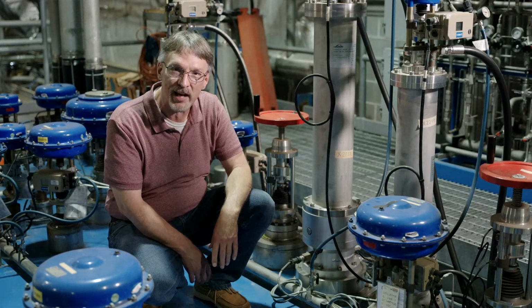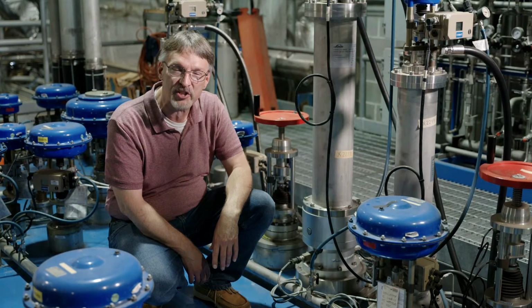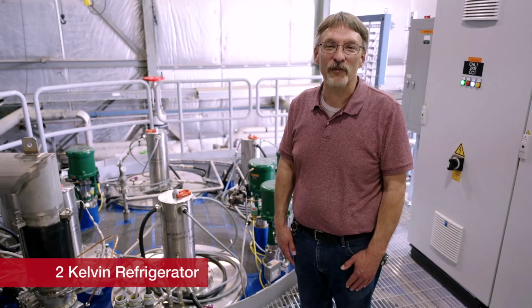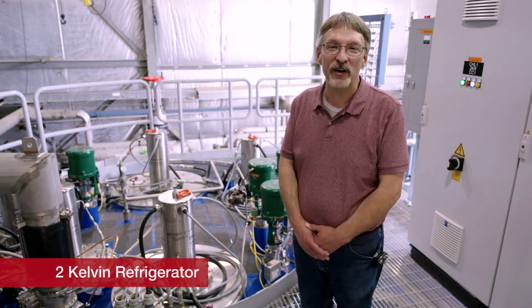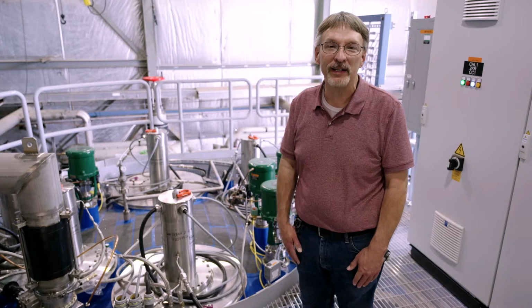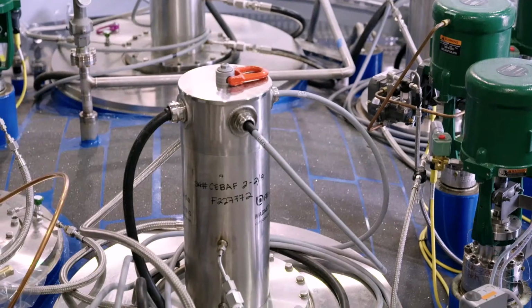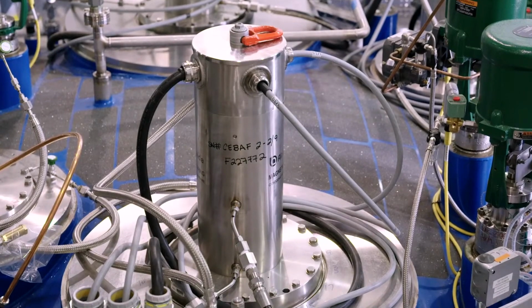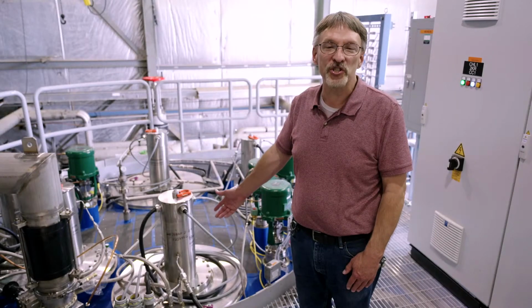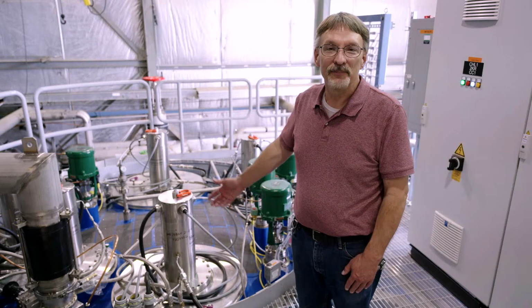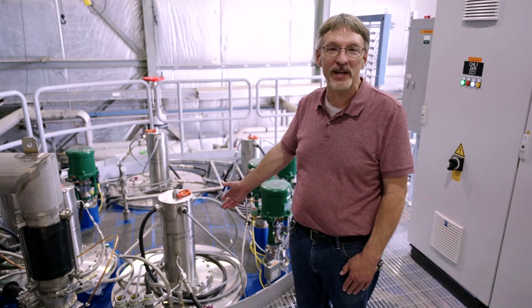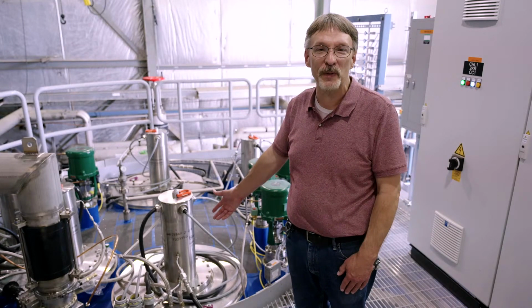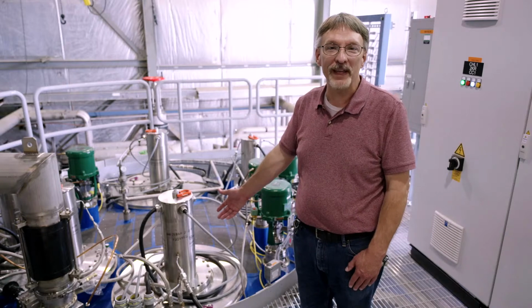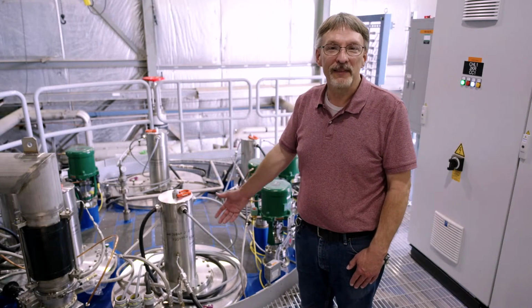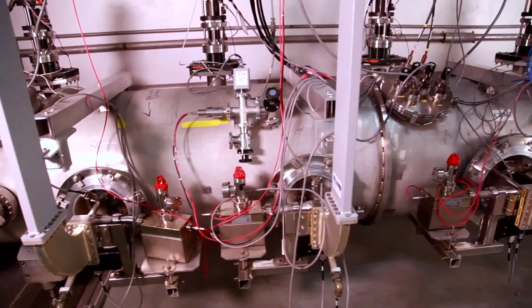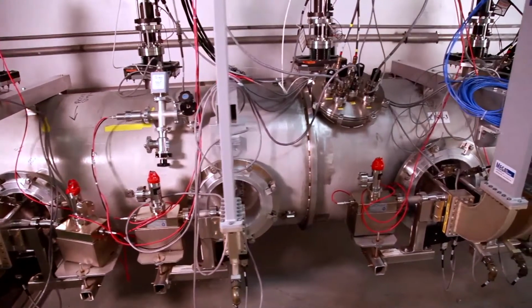Next, we're going to go to the 2 Kelvin machine, the last part of the refrigeration process. Now we're on top of the 2 Kelvin refrigerator. Normal helium at 1 atmosphere is 4.5 Kelvin. This machine lowers the pressure from 1 atmosphere to 0.039 atmospheres, which is 2.08 Kelvin. It does this using these 5 cold compressors, which spin at speeds of up to 50,000 RPM, and they draw a vacuum on the helium that lowers its pressure. The 2.08 Kelvin helium is then used to cool components which are in the main accelerator.